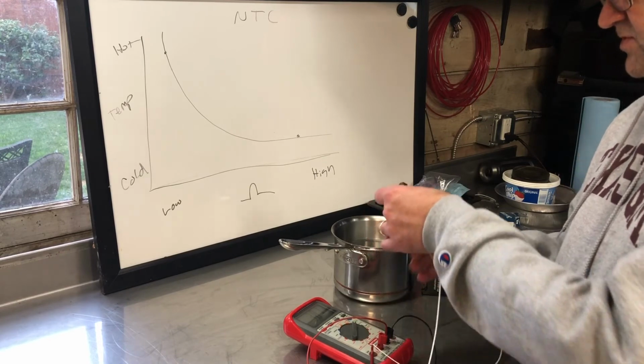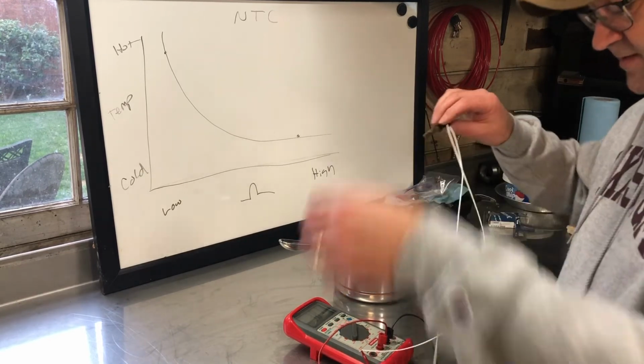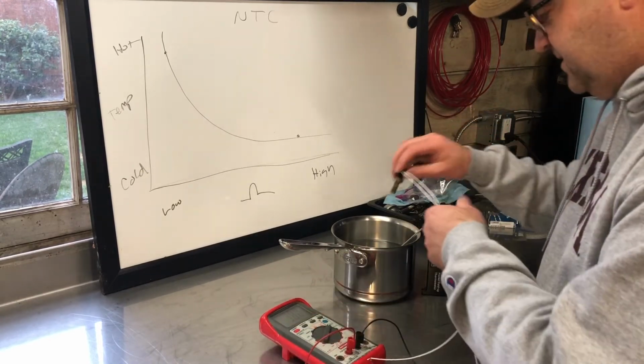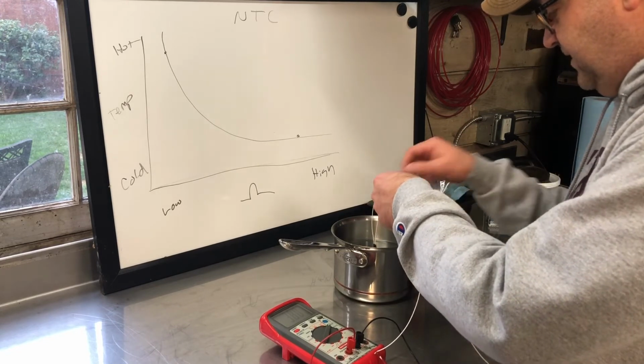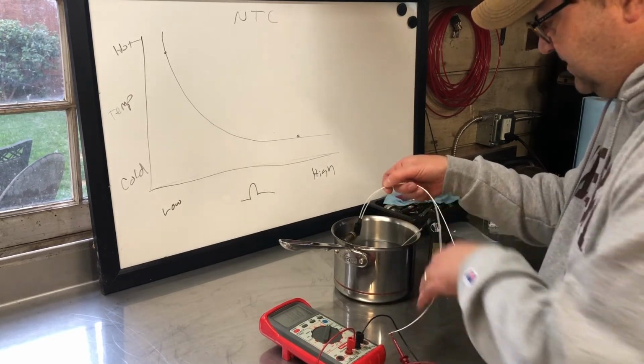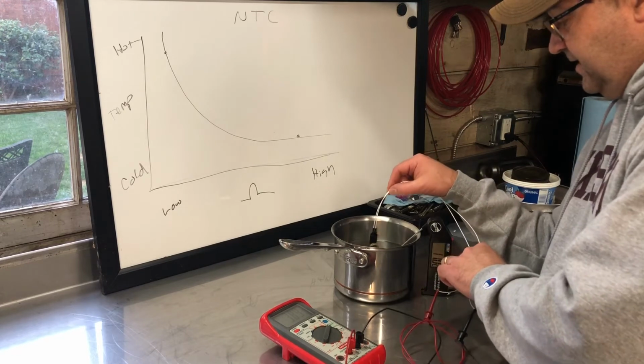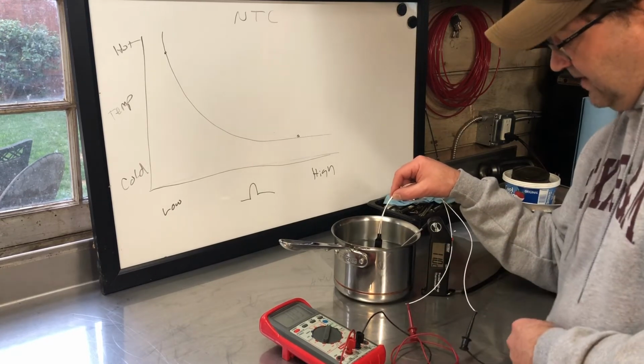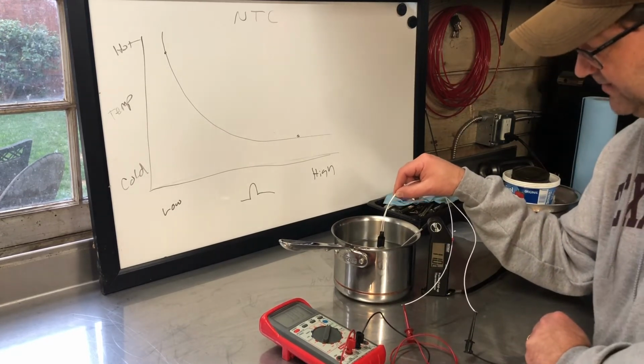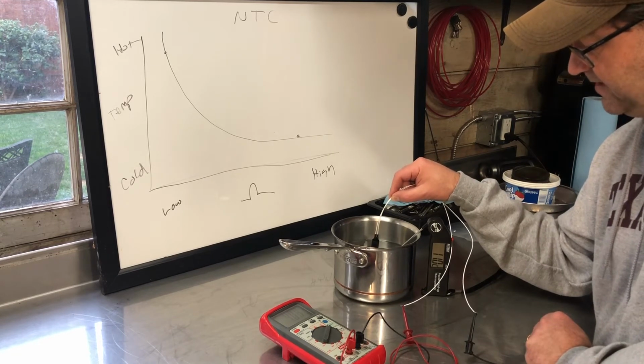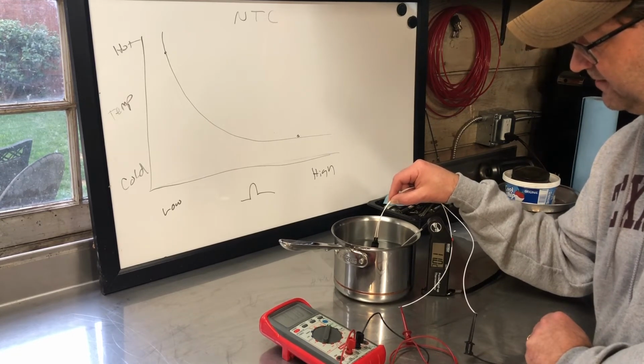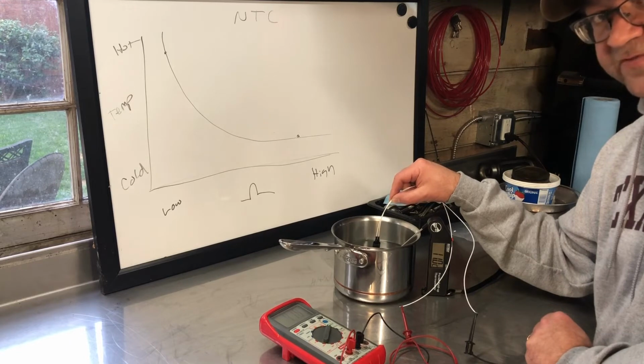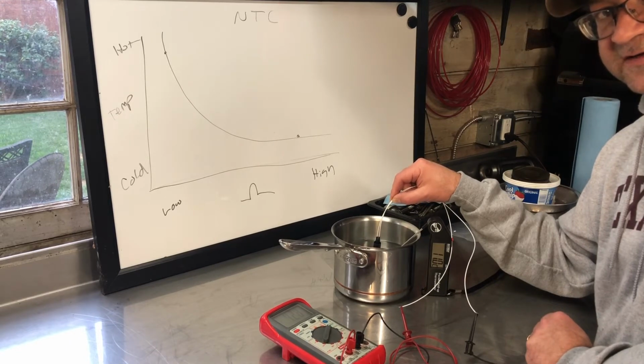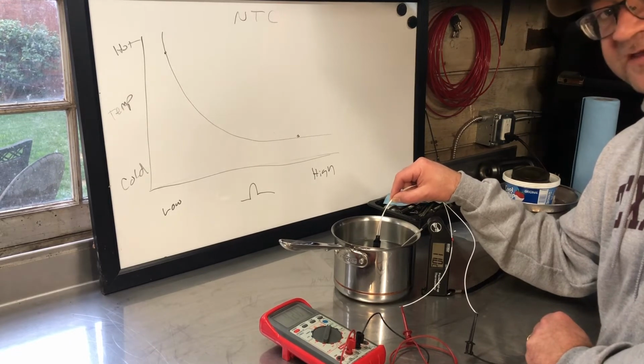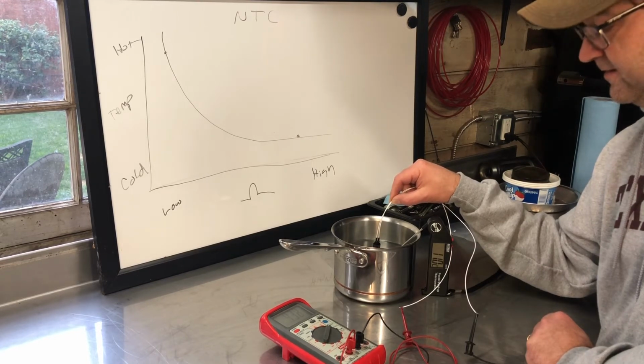I've got my temperature sensor leads hooked up to the multimeter and set to measure resistance, and I'm just going to hold this here so it doesn't get completely submerged, and wait until it gets stable. It's better to do this with a fairly large amount of water, because the more thermal mass you have, the slower it's going to change temperature, and it'll make things settle out easier and make it easier to get an accurate reading.